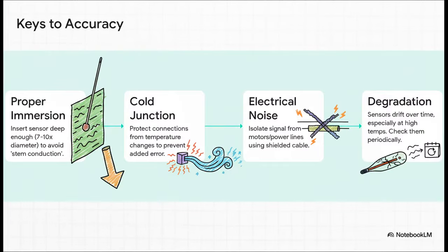Number 1, proper immersion. You have to stick the sensor in deep enough. The rule of thumb is at least 7 to 10 times the probe's diameter. If you don't, the metal sheath can actually pull heat away from the tip and give you a reading that's way too low. 2. Protect the cold junction. That's just the spot where the sensor wires connect to your meter. If that connection point gets hot or cold, that temperature change gets added directly to your reading as error.